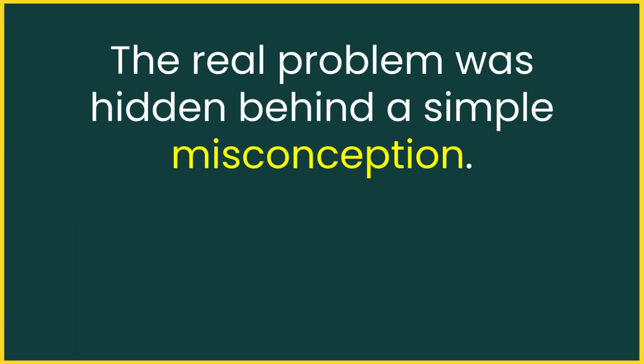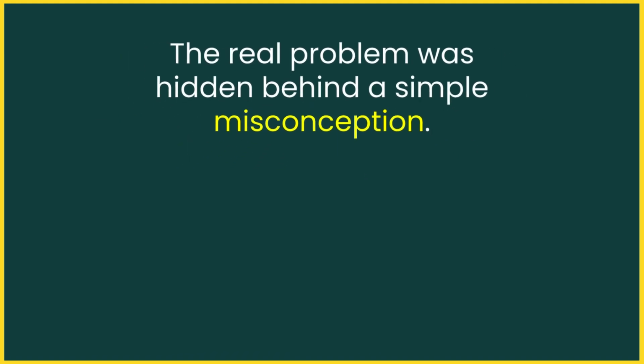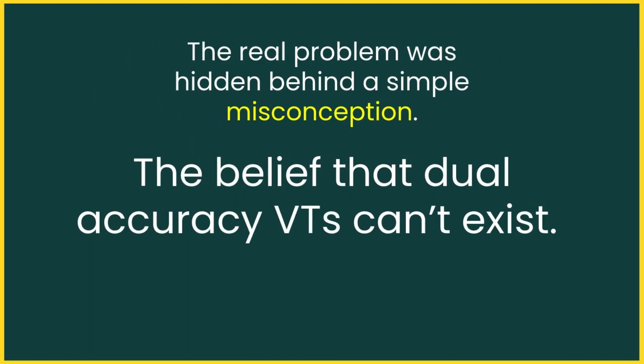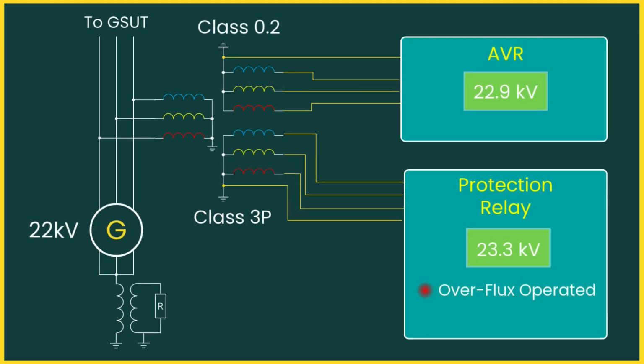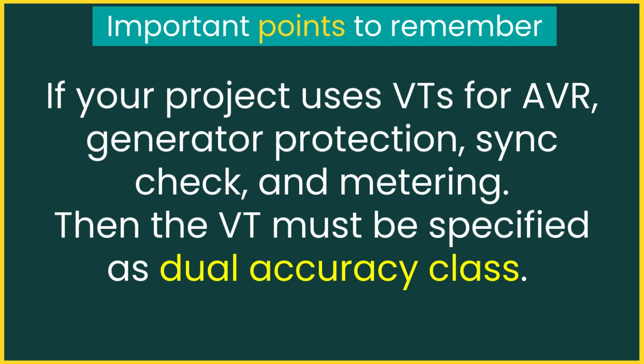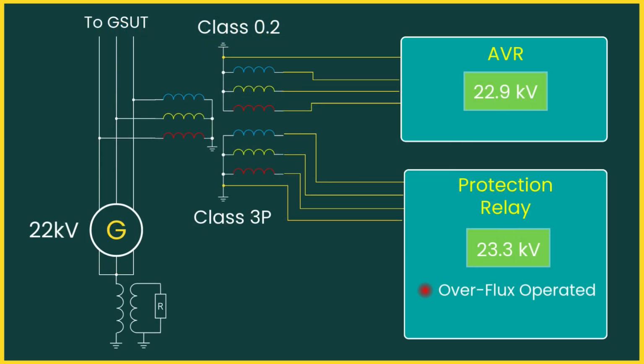The real problem was hidden behind a simple misconception: the belief that dual accuracy VTs can't exist. In this case, the AVR read voltage accurately with the 0.2 class VT. But the protection relay misread it due to the large error of the 3P class VT. So, if your project uses VTs for AVR, generator protection, sync check, and metering, then the VT must be specified as dual accuracy class. Otherwise, one device will read correctly, and the other will misread the generator voltage and trip.